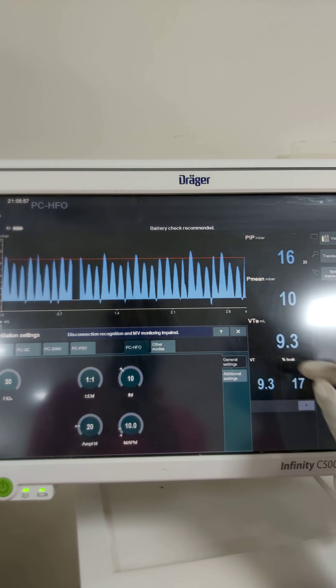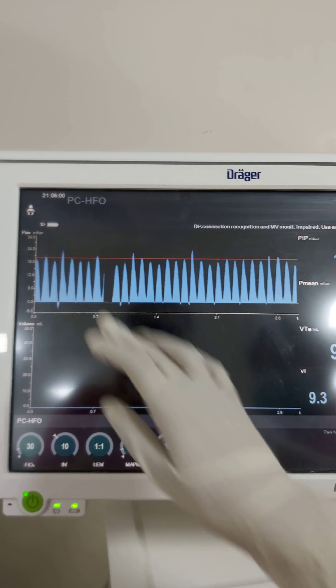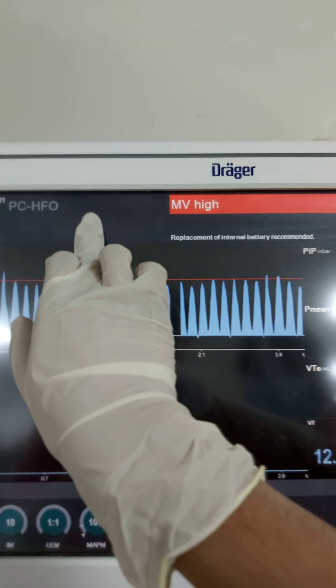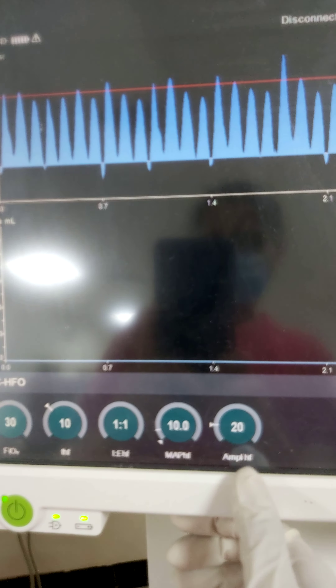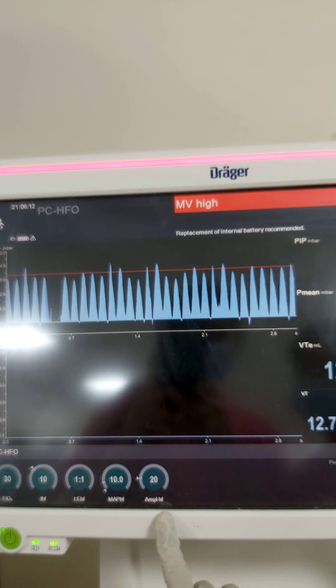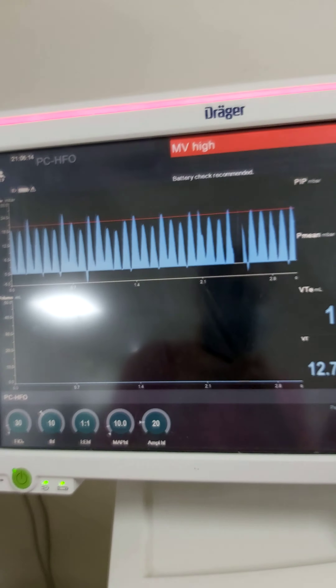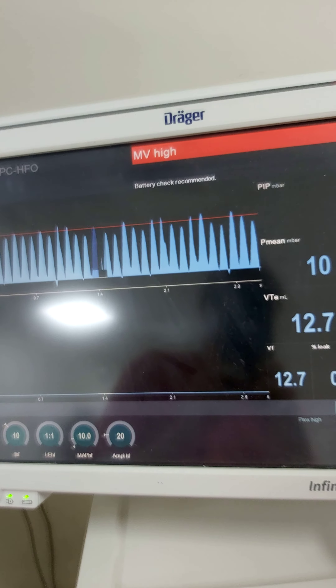The high frequency ventilator is now running. FiO2 is 30%, frequency is 10, MAP is 10, and amplitude is 20 — double the MAP value. Thank you. I appreciate the preparation.